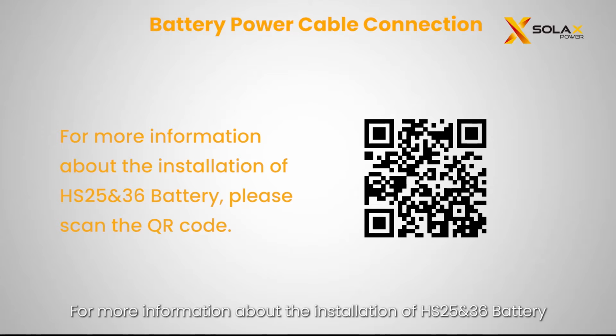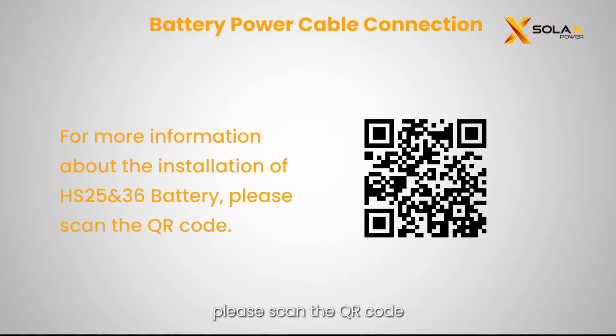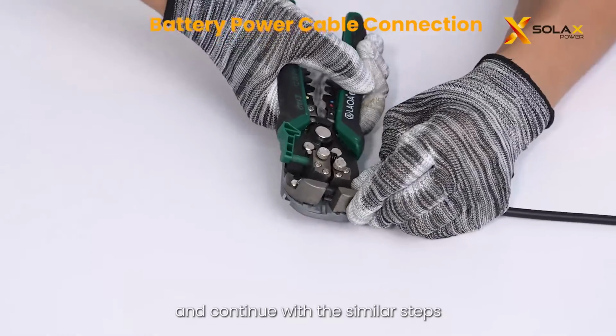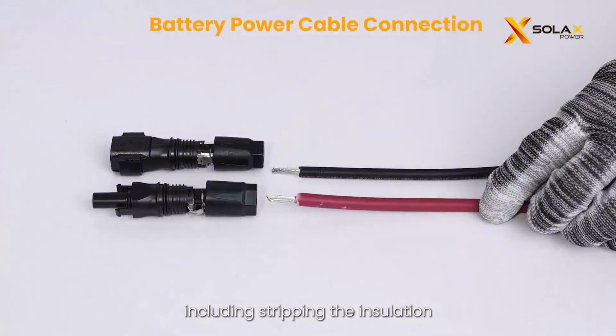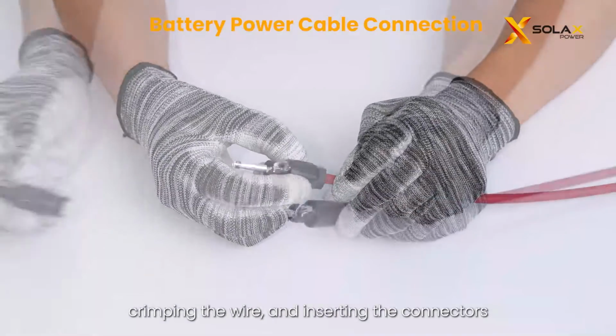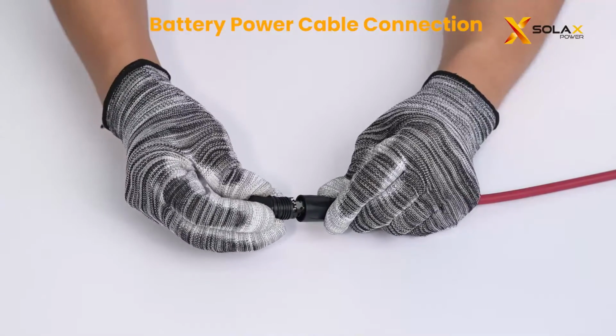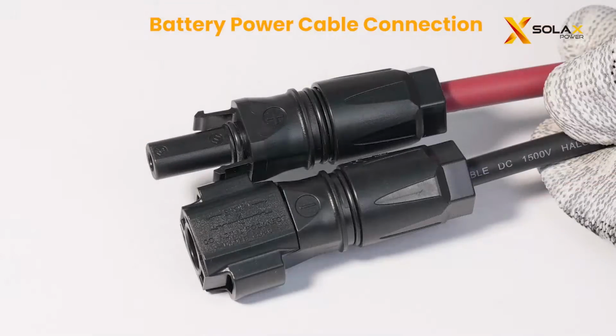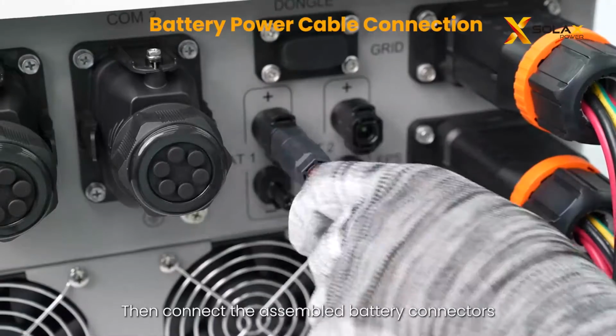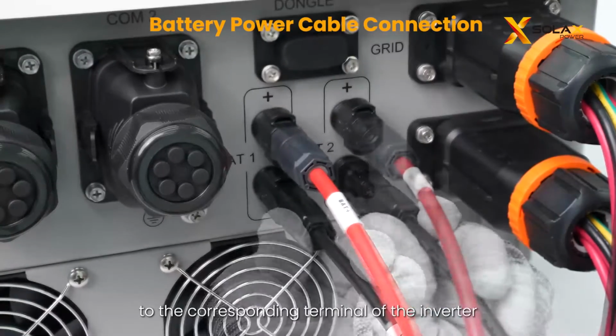For more information about the installation of HS 25 and 36 battery, please scan the QR code. Get the battery power cables ready and continue with the similar steps, including stripping the insulation, crimping the wire, and inserting the connectors. Then connect the assembled battery connectors to the corresponding terminal of the inverter.